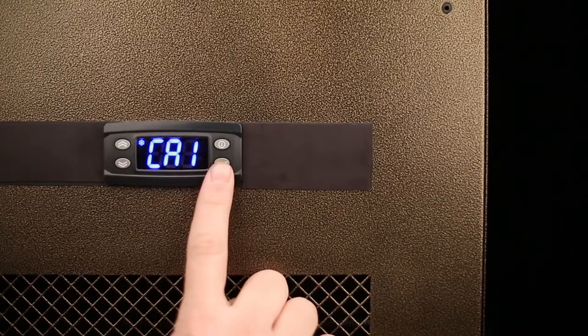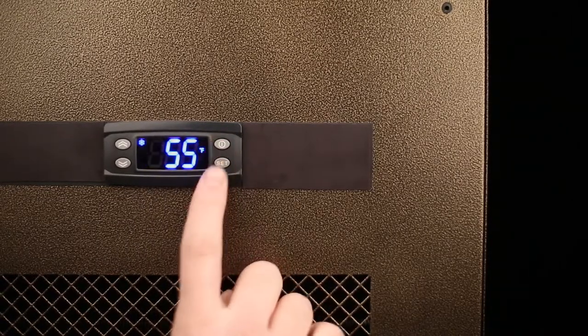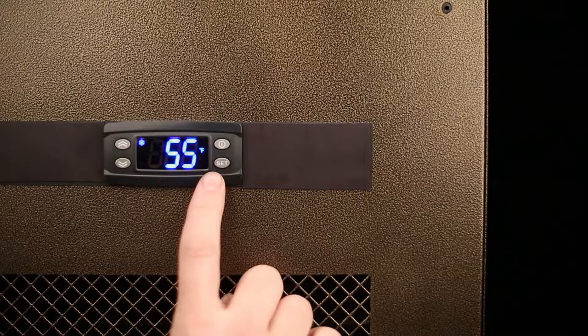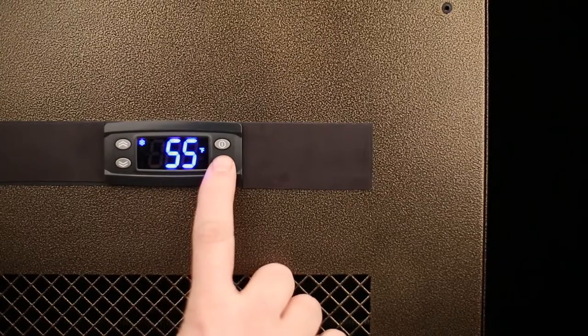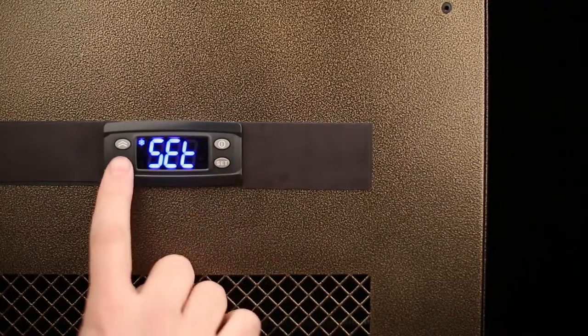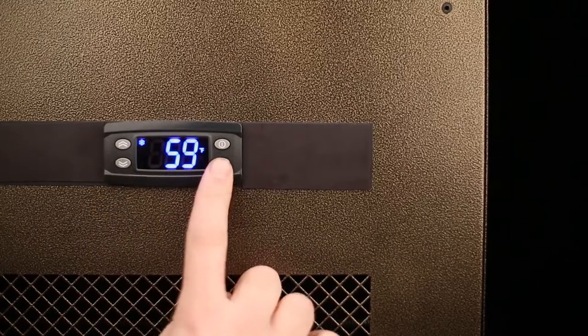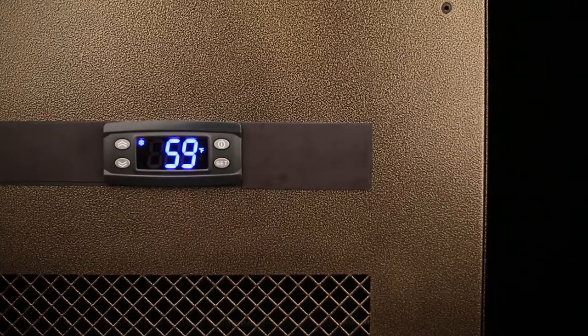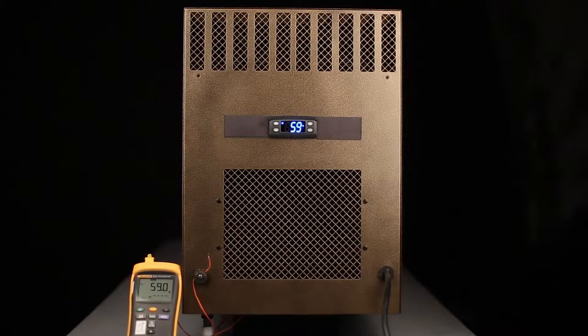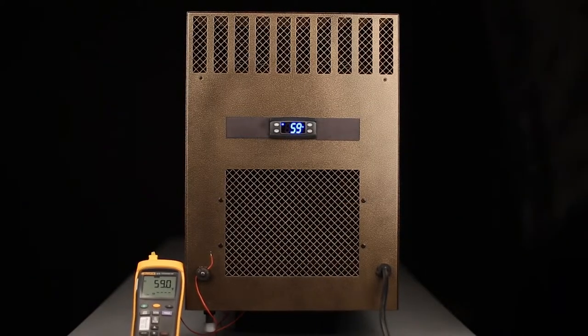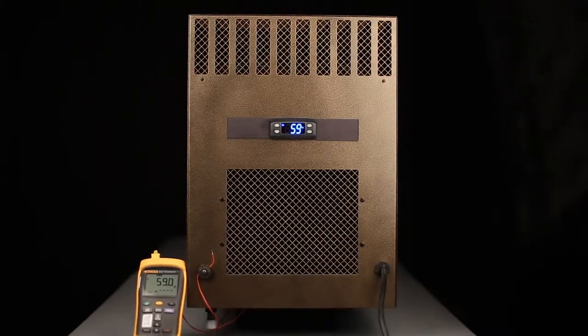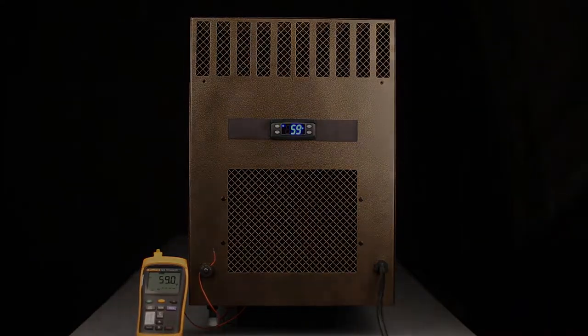To verify the temperature sensor on the cooling unit and external thermometer are reading the same temperature, press the set button once, scroll down to the CA1 parameter, and press the set button again. If both the temperature on the controller and the temperature on the external thermometer are in agreement, you know that you have successfully calibrated the sensor on the cooling unit to the external thermometer.